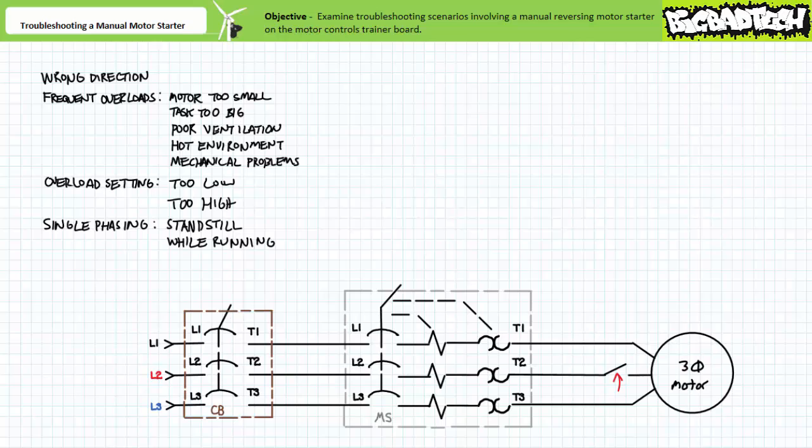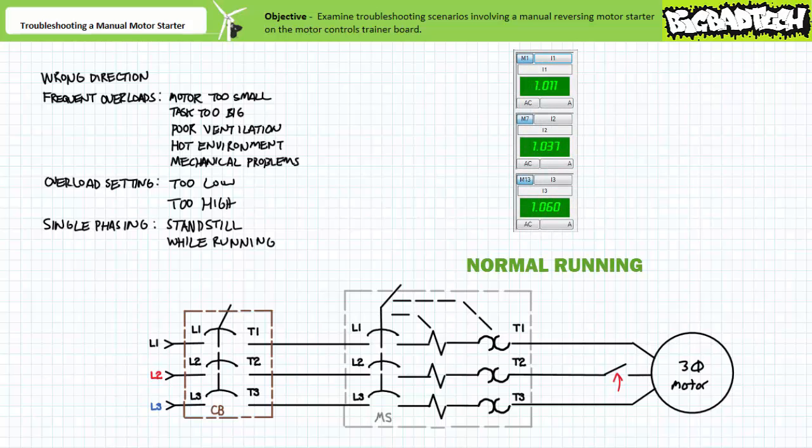The easiest and most non-invasive way to determine which phase is lost is to use an amp clamp or take voltage checks. Here's an amp clamp being used to measure line current of a properly running three phase AC motor. Note they're all relatively equal because the system is balanced. Now, here's an amp clamp being used to measure line current of a three phase AC motor that's been single phased while running. Note current in L1 and L3 are too high and L2 is carrying no current. Phase L2 is obviously the source of our problem.